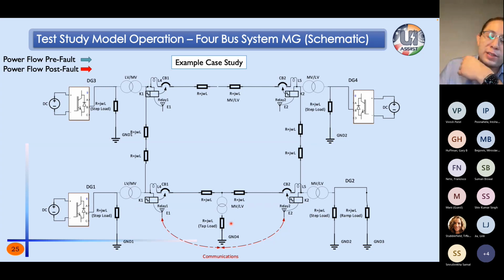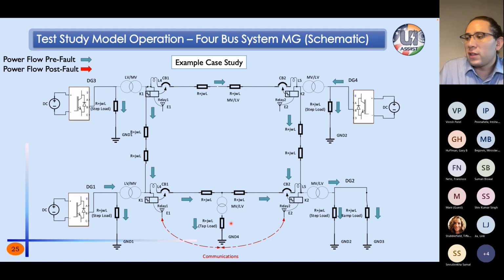In this example, I'm showing the test case study model for a fault. This is the same one-line diagram I showed before. In the blue line, I'm showing how the power flow operates. This is the pre-fault case, and we can see how the power flow goes from each inverter towards each load across the whole microgrid in this array. But suddenly a fault happens at this point. If we have a fault here, our currents will shift. We will see that the currents after the fault are different if the fault is not cleared. We can see there is a change in direction on the right-hand side, going from right to left. That means we are feeding the fault. This gives a way of analyzing the grid as a differential type of relay method, like the one I showed in the previous slide, and this opens a new set of studies for distribution grids.